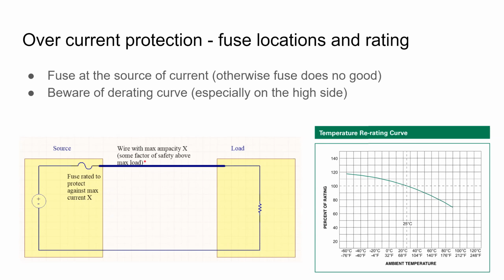I think 14 gauge will go up to 15 amps, at least for houses. So make sure the ampacity of the harness is higher than the fuse rating, because if you have a harness where the insulation starts smoking before the fuse trips, you'll be very sorry.